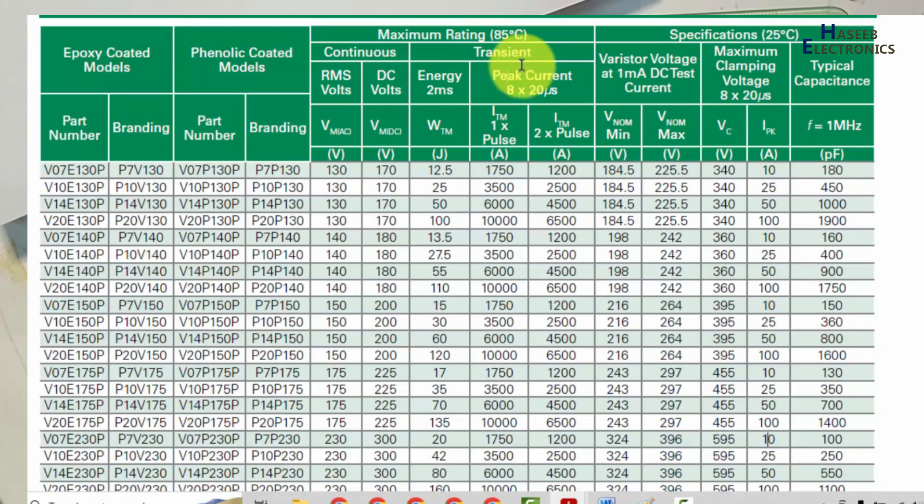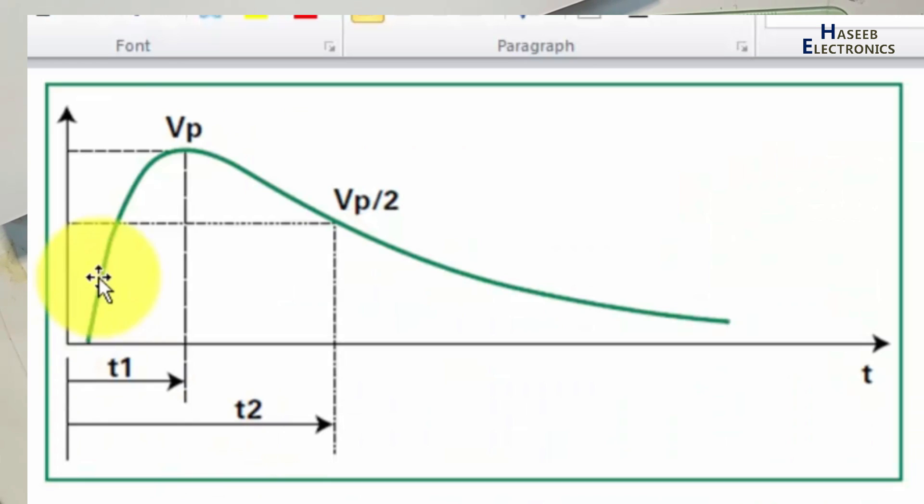Here is now transient condition. If any transient, any pulse will arrive - 8 by 20 microseconds. That means if any pulse starts from t0 and reaches up to 90 percent of its peak - from t0, from zero line to 90 percent of the peak, it is called t1. If any pulse will reach at 90 percent in 8 microseconds, so this is first time.